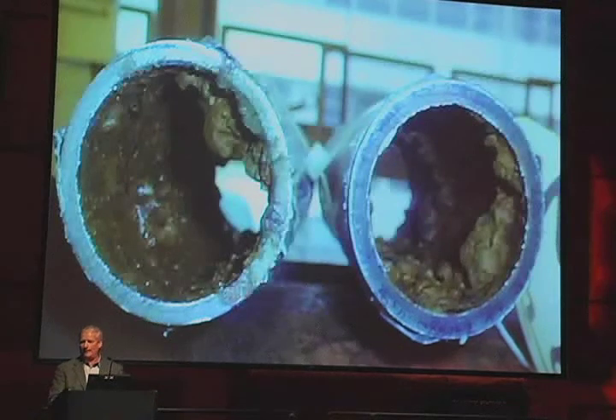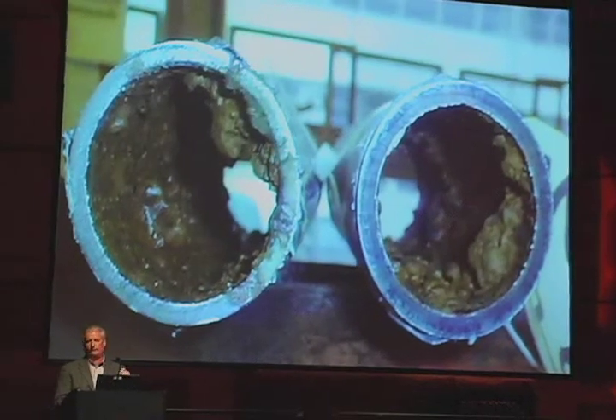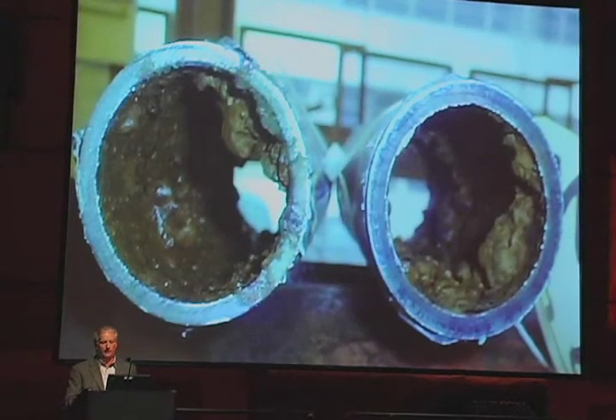Pipe does not want to be in the natural state of iron. It wants to be rust. That's its natural state, so it wants to go back to that natural state. And we help it by using water and other corrosive environments, so it actually corrodes quickly. So the problem is in these closed loops, if you don't take care of them, they actually start restricting flow through the systems, and then you lose heat transfer efficiency on the equipment.